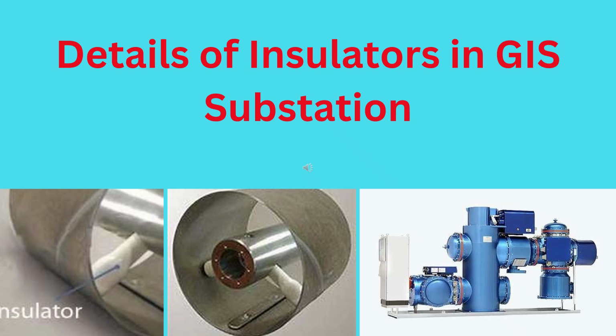The conductors or live part shall be mounted on high-graded epoxy resin insulators. These insulators shall be designed for high structural strength and electrical dielectric properties. It shall be properly shaped to provide uniform field distribution and to minimize the effects of the particle deposition either from migration of foreign particles within the enclosure or from the byproducts of the SF6 breakdown under the arcing conditions.